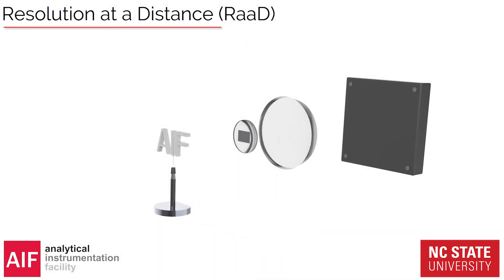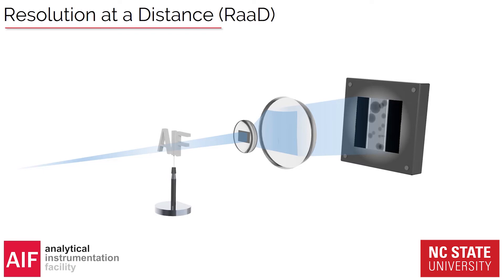There's another nice thing called resolution at the distance — I think it's still somewhat proprietary — where instead of putting the scintillator directly on the pixels, you put the scintillator on top of an objective. The scintillator creates visible light that you can use objectives to magnify a lot. So with this type of setup you first have geometrical magnification and then optical magnification as well, which allows really high magnifications — something not really achievable with projection-style magnification alone. This is something we can do in the X-Radia machine.